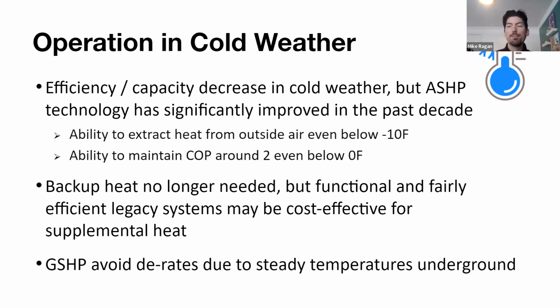Daikin has their Aurora series, Mitsubishi has our Hyperheat line of equipment. Effectively, all of these use flash injection, vapor injection technology for our compressors. This is an improvement that allows for additional ability to extract heat from outside air, even at temperatures below -10 degrees. Between Daikin and Mitsubishi, who's represented on this call, we have published data for our outdoor equipment down below -20 degrees. That's not exactly a temperature we're going to see often in New England. In fact, it'd be very concerning if overnight we saw lows 20 degrees below what we typically see. But nonetheless, the equipment that we sell is capable of extracting heat from that air even as low as -20 or even further.